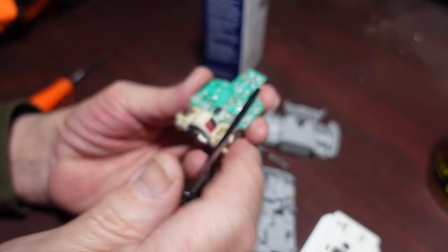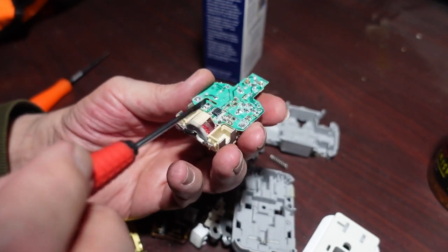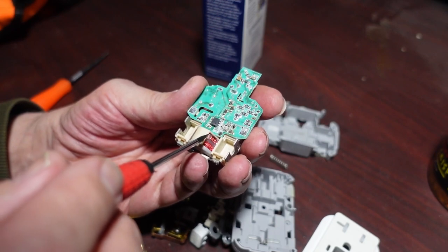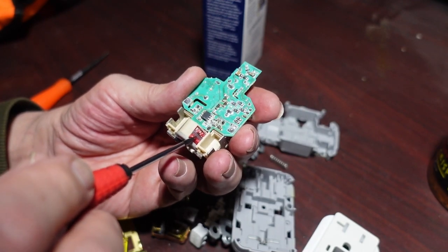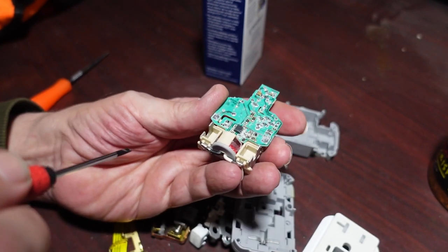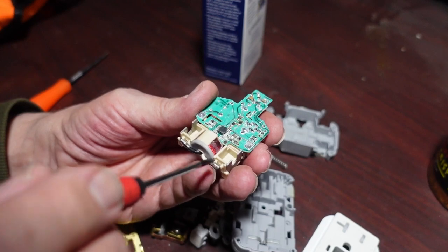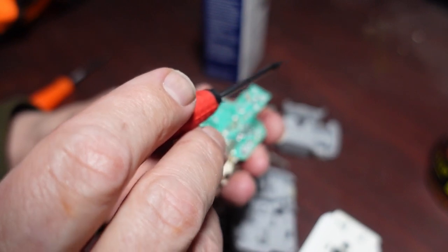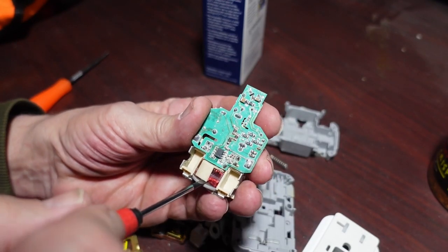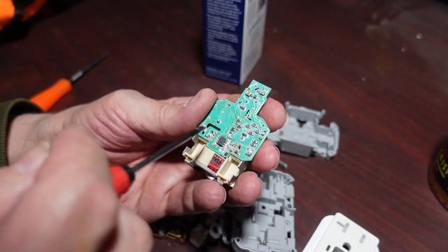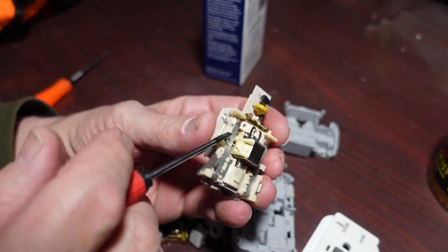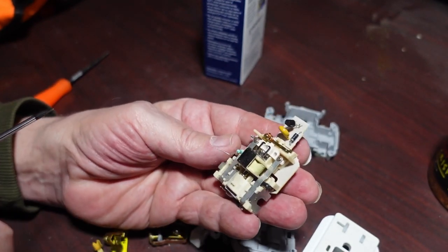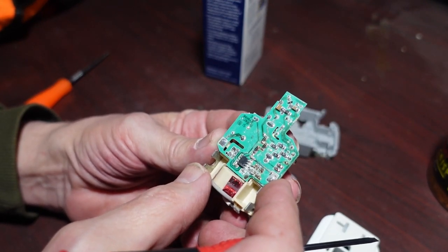I believe these are sense coils in here that are like current transformers. They get a voltage depending on the current that's flowing through both legs of the circuit. If the current going in matches the current going out, then they cancel each other out and nothing happens. But if, for instance, the hot wire runs into something and is shorted to ground, then that's a ground fault condition. One of these is much higher than the other, so that shows a potential, and that triggers a little actuator in here that springs and opens these contacts. It's a nice clever design. I just didn't realize there was that much electronics in there.